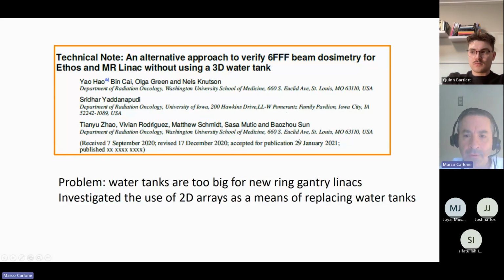This is a paper that was published in Medical Physics just a couple of years ago, and the problem that people in this paper were trying to solve was, how do you do good dosimetry on an inline machine that doesn't have enough space within the bore to fit a water tank. So they're looking at an alternative approach to verify the 6 MV FFF beam dosimetry for an Ethos machine. An Ethos machine is a new style. It's an O-ring machine, not a C-arm gantry, and you don't have enough space to fit a water tank onto the machine.